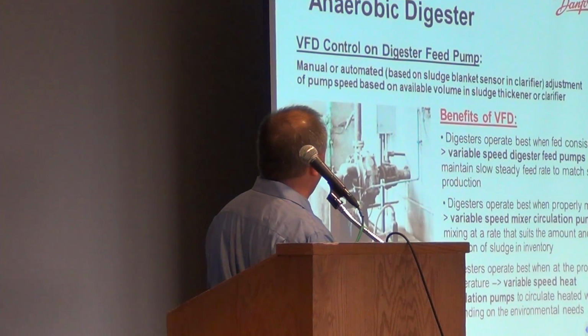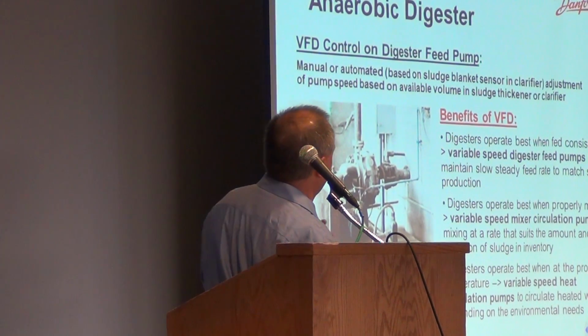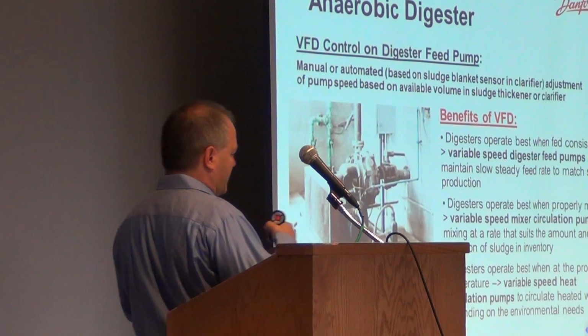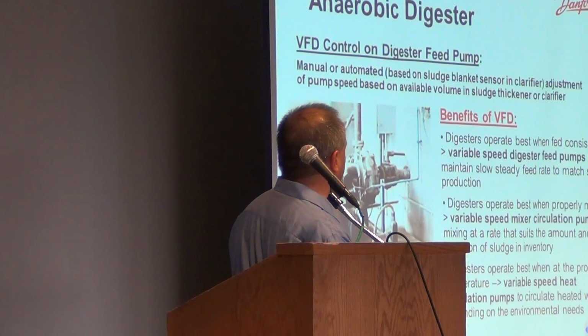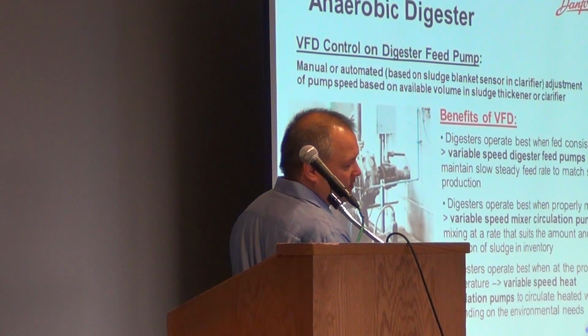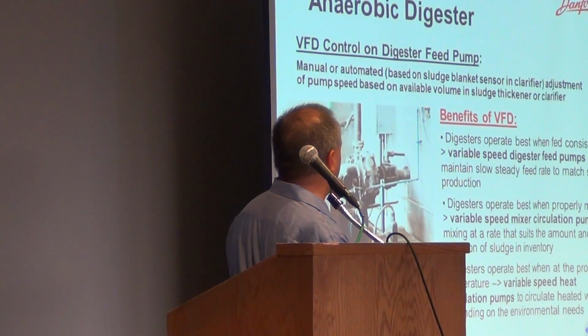We're talking about the continuous flow of feeding the digesters. With the VFD, we can get a continuous feed of fluid and sludge so that it actually operates at the optimum of that digester. We're not slugging the system, we're not giving it too much and not enough.